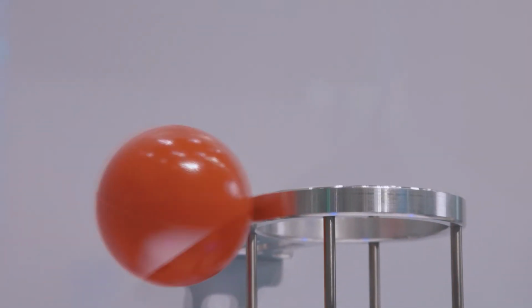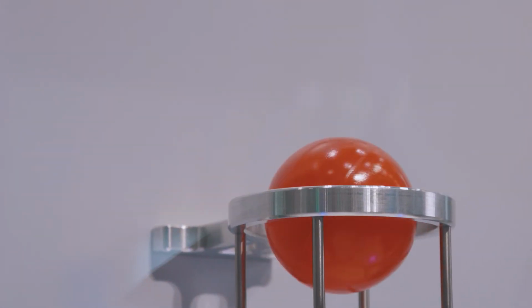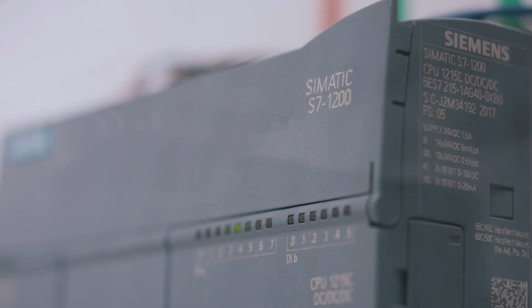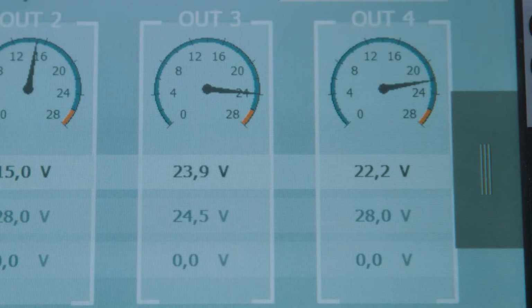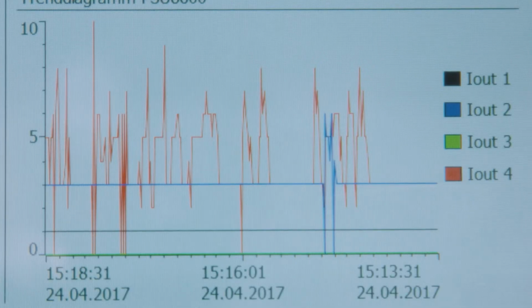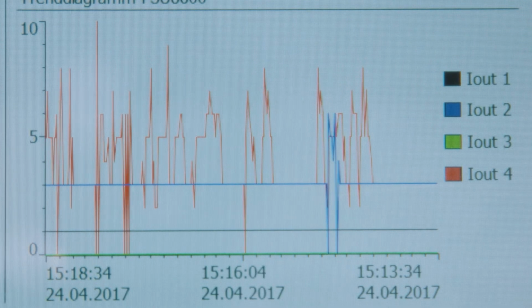Siemens S7-1200 transfers the target value of the output voltage to the power supply via Profinet. It calculates the target value based on the signal of the manual control. Since SITOP PSU8600 reacts nearly in real time to the target value, the output voltage is directly changed when pressing the manual control. And as it continuously measures the power and voltage of all outputs, we can display the development via faceplates. In doing so, the current energy consumption can be identified and used for energy management.